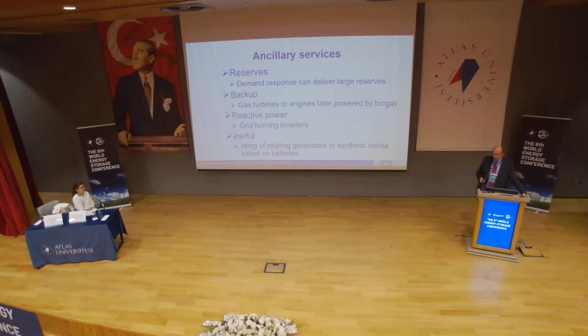We will also need to solve the problem of reactive power for voltage control, and grid-forming inverters are a solution for that. I hope the Spanish will learn from their mistake, because they didn't force the inverters to provide reactive power, and that's why they had this blackout.